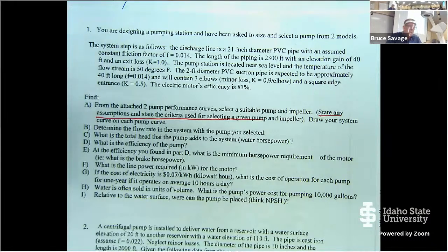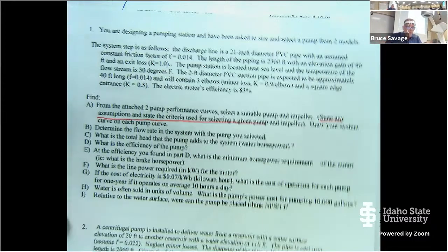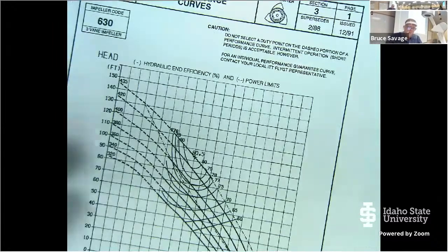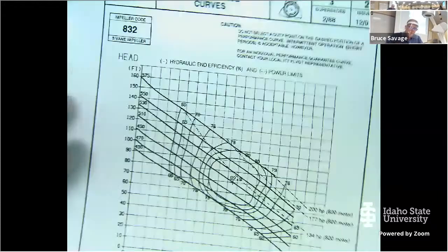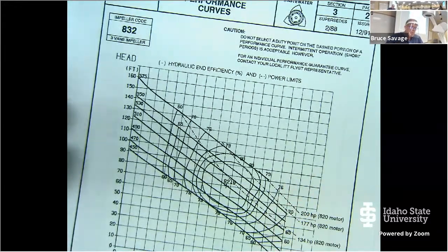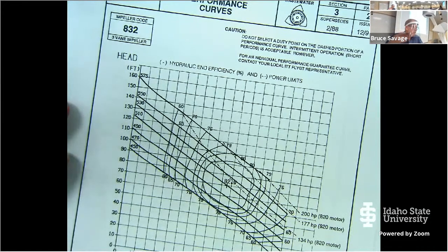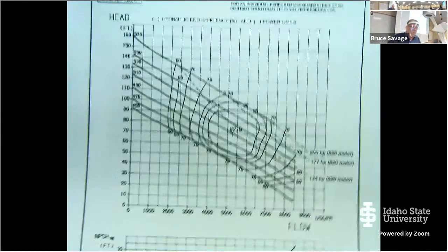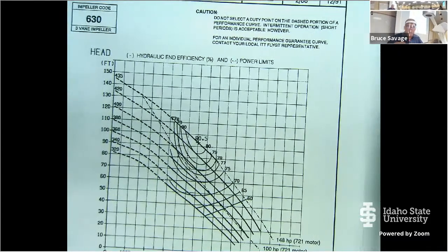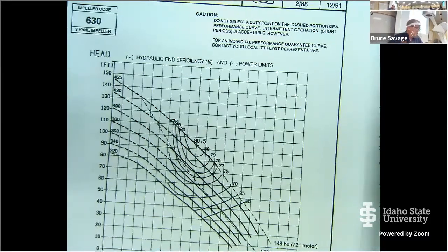And that could mean that either one of those pumps will meet the criteria of what we need. The one that pumps more, this one's going to max out around 8,000 or so. This one maxes out about the same. So we're not worried. Obviously, this pump is going to come on when we need it and turn off. It's not going to be running continuously. So 8,000 gallons per minute must meet the criteria of whatever we're putting into. So pumping is not one of the design parameters. Now you need to just decide what is going to be your parameter, and efficiency would be the obvious choice. Okay.